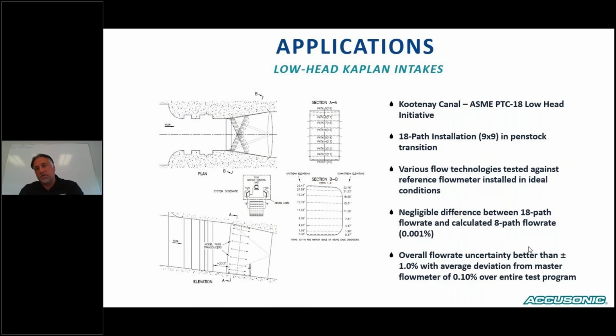And we utilized, instead of a 4x4 8-path system, we installed an 18-path system. So it was basically 9 chordal elevations, cross paths. We were in the transitional section from the rectangular section to the penstock. The ASME PTC 18 actually tested a number of different technologies, and everything was referenced to a master meter that was installed about 20 to 25 diameters downstream in perfect hydraulic conditions. And the nice thing about this is it was blind testing, so we didn't know where we were stacking up with the master flow meter.